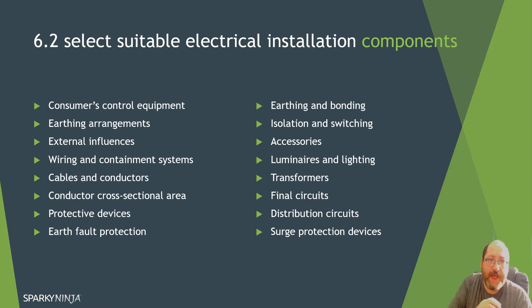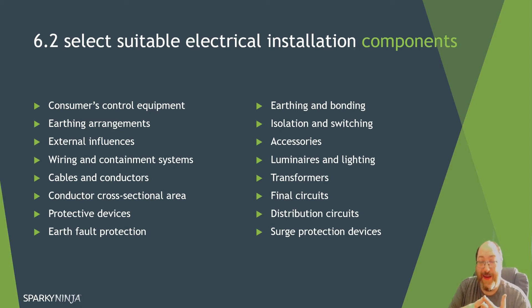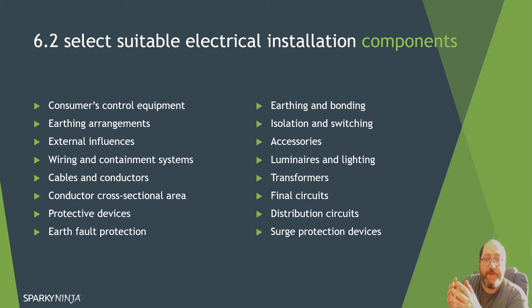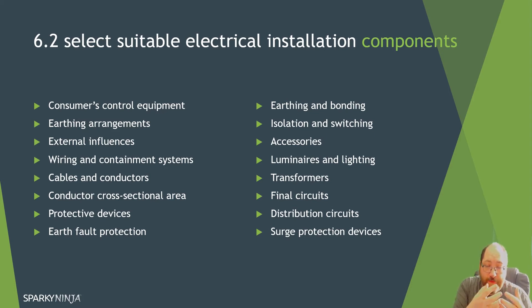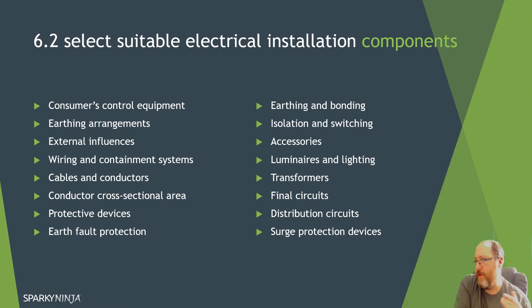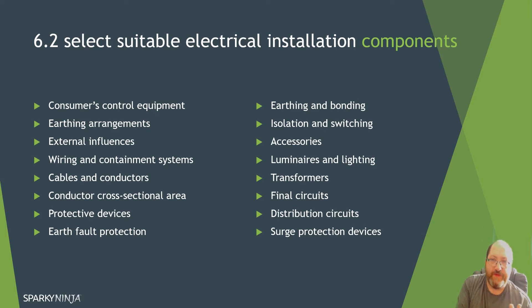Cables and conductors: decide your cable types. In your design you'll state the cable type, thermal limits, volt drop, and even the manufacturer — capturing a data sheet to support your decision-making is great. Conductor cross-sectional area must be proven with accurate calculations. For protective device types, decide why you'd choose one type over another — ensure you achieve suitable protective devices. You may need to determine what additional protection is required and what protective measures are in the installation, as that may dictate device selection.